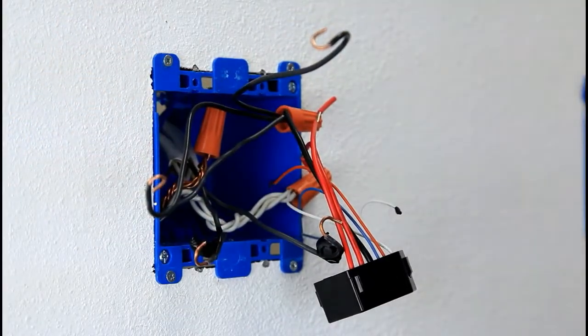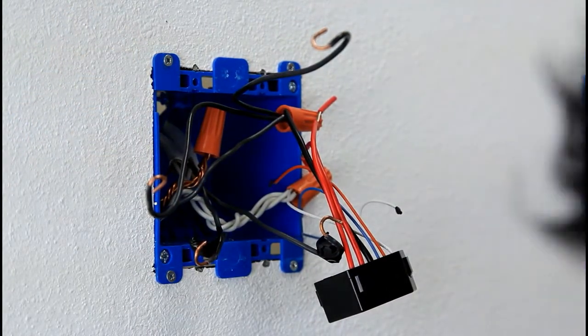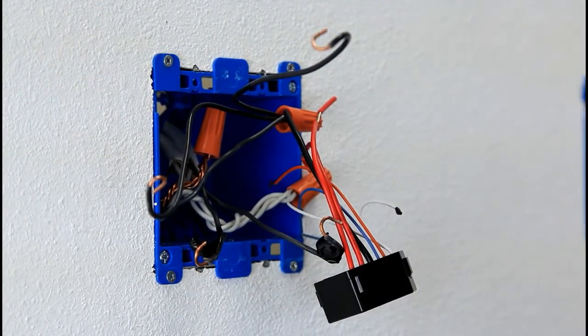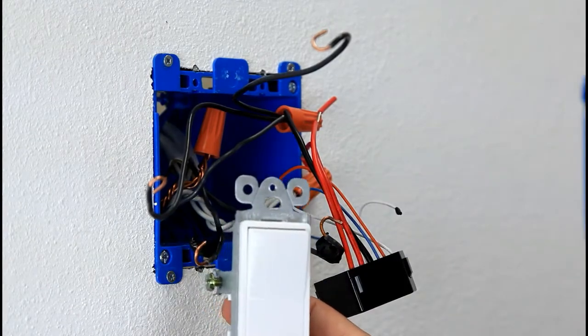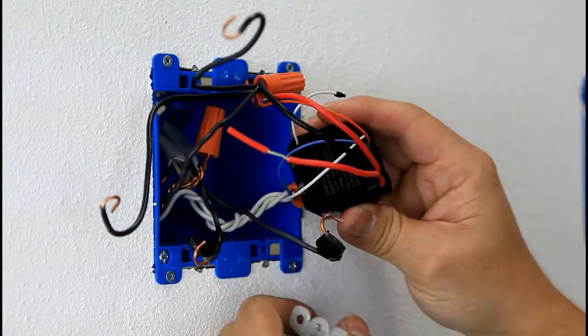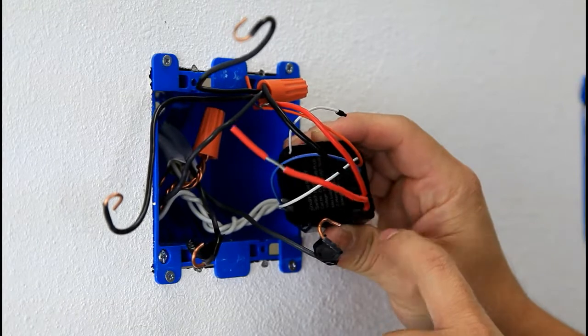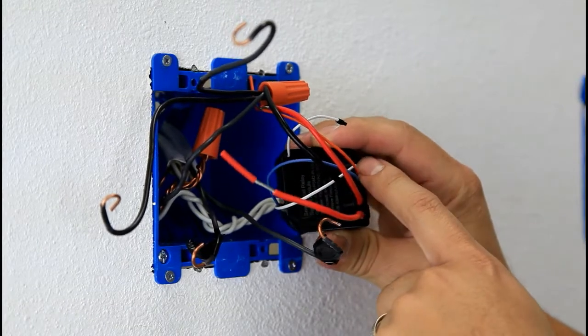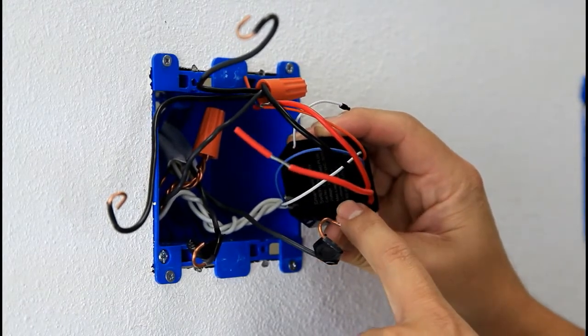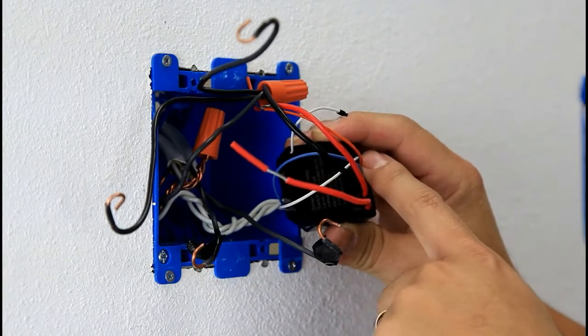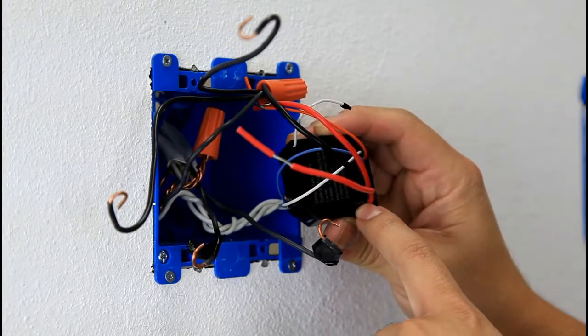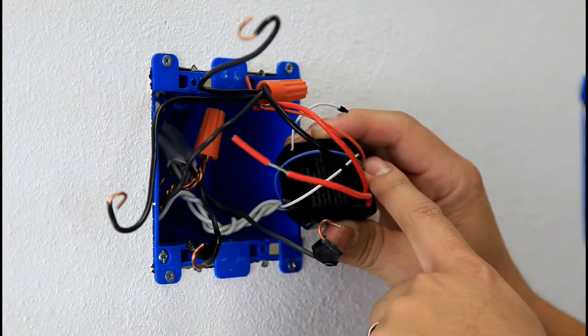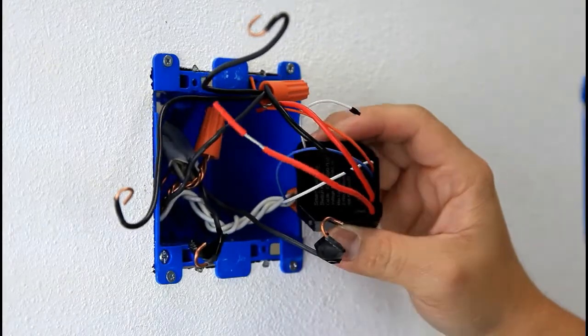So we're going to go ahead and reconnect the wire back to your switch number one. On the relay, it has an L1 and L2, same as the auxiliary 1, auxiliary 2. Just make sure you use the same one. If you're going to use L1, make sure you use auxiliary one. If you're going to use L2, use auxiliary 2 for each of the switch.